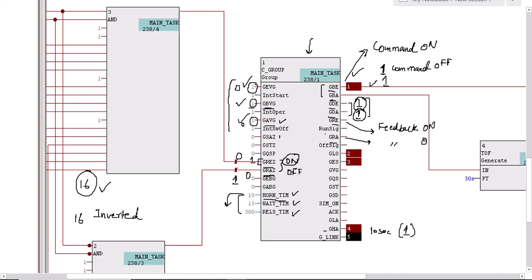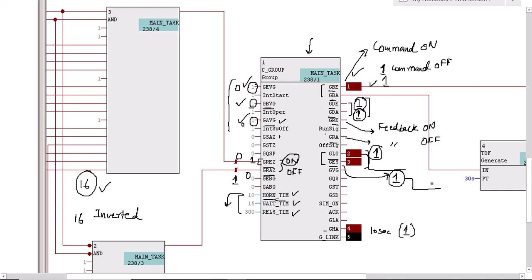GLO and GES relate to operating modes. Devices can operate in local mode, single mode, or automatic mode. If the operator selects local mode, GLO will be one, and this is linked with each C Drive block so all devices go to local mode. GES stands for single mode — when the operator selects single mode, a one signal is initiated and interlinked with each C Drive block so all equipments go to single mode. If both GLO and GES are zero, the group is in automatic mode.